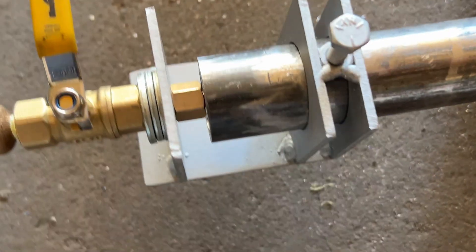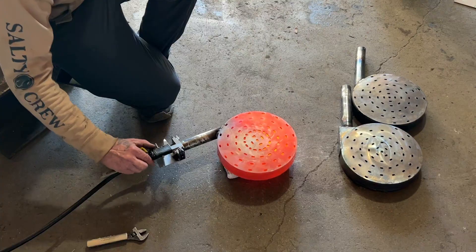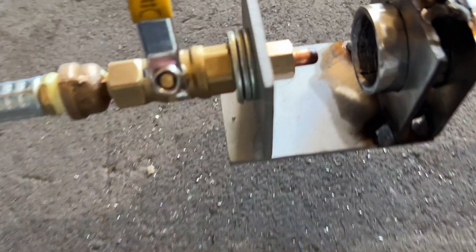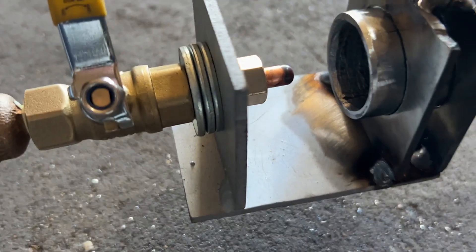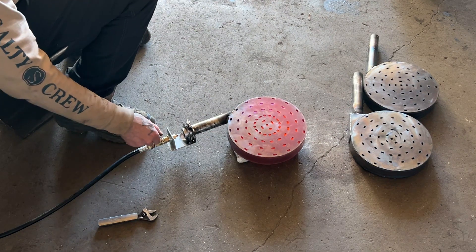You can see the one that has this square body in it likes to be about right there on the valve. There's a 17.5 millimeter gap in between the nozzle and the venturi port. See here how this nozzle screwed in, because this is going to be shipped disassembled — that's basically the gist of it. Lights right up.